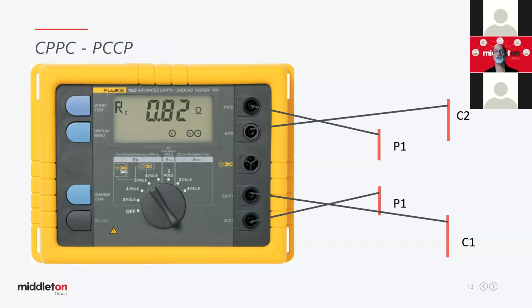And amazingly enough, you'll come up with the same reading. I can explain that in question time if you like. So we should get the same reading. So you push it one way and push it the other. If there's any DC stray currents or errors in the ground, when we average this will help cancel those errors.